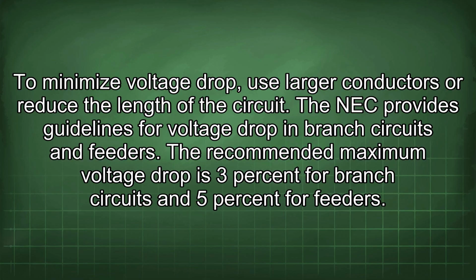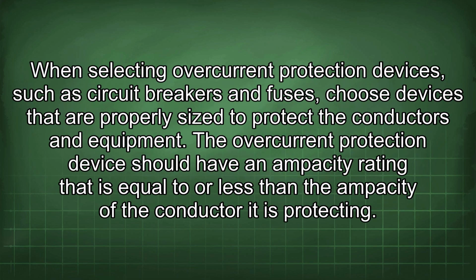The NEC provides guidelines for voltage drop in branch circuits and feeders. The recommended maximum voltage drop is 3% for branch circuits and 5% for feeders. When selecting overcurrent protection devices, such as circuit breakers and fuses, choose devices that are properly sized to protect the conductors and equipment. The overcurrent protection device should have an ampacity rating that is equal to or less than the ampacity of the conductor it is protecting.